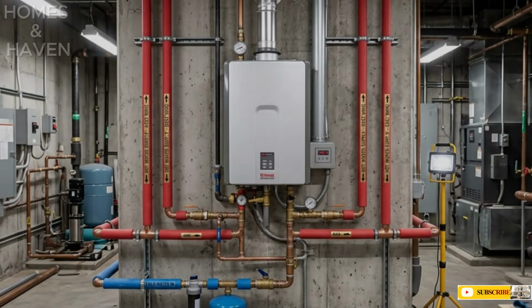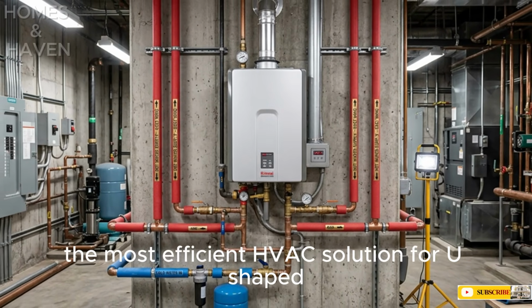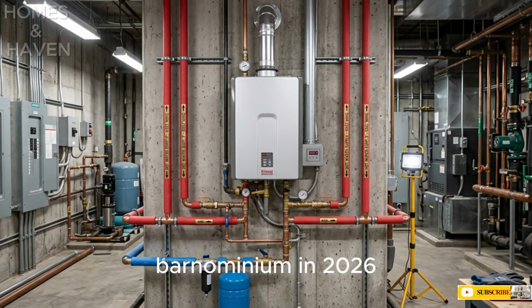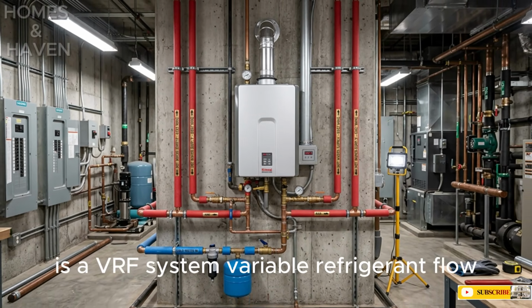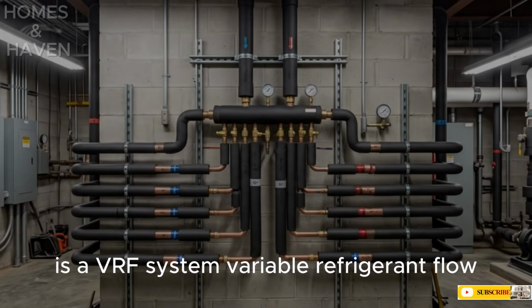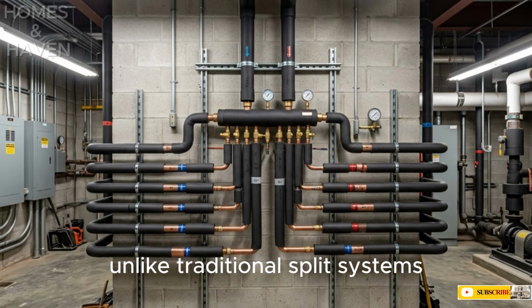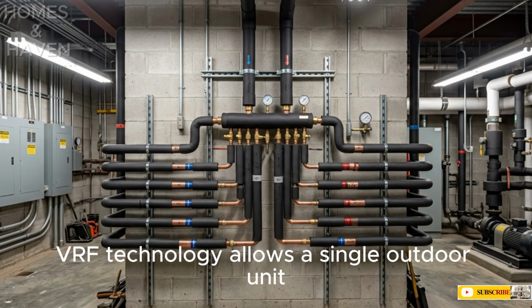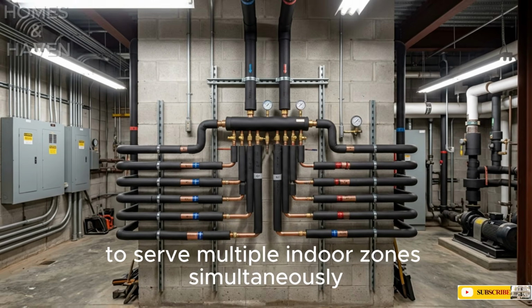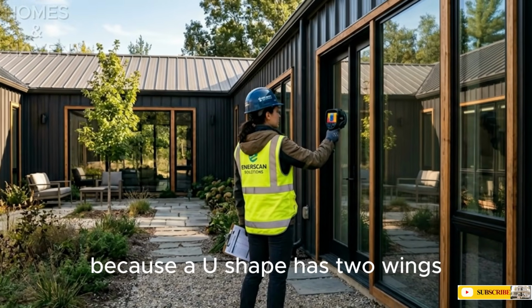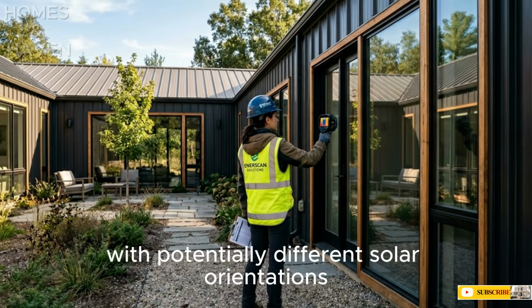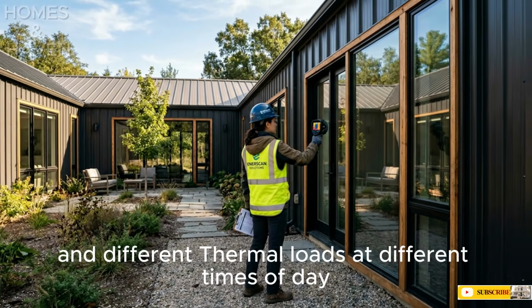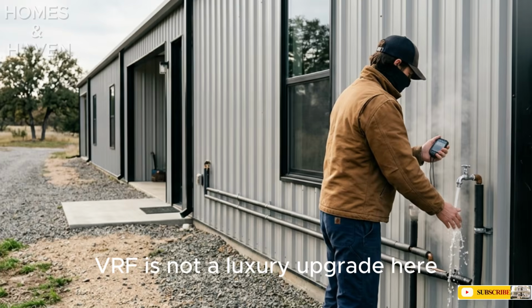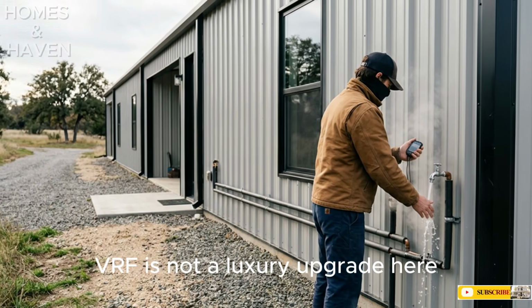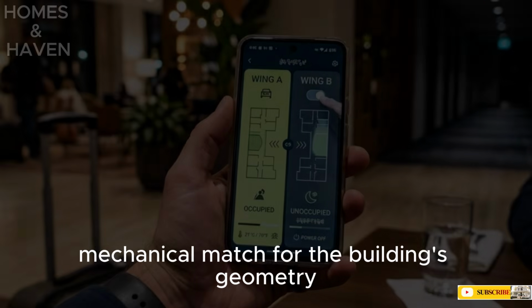On the mechanical side, the most efficient HVAC solution for a U-shaped barndominium in 2026 is a VRF system, variable refrigerant flow. Unlike traditional split systems, VRF technology allows a single outdoor unit to serve multiple indoor zones simultaneously, with each zone independently controlled. Because a U-shape has two wings with potentially different solar orientations and different thermal loads at different times of day, VRF is not a luxury upgrade here. It is the logical mechanical match for the building's geometry.